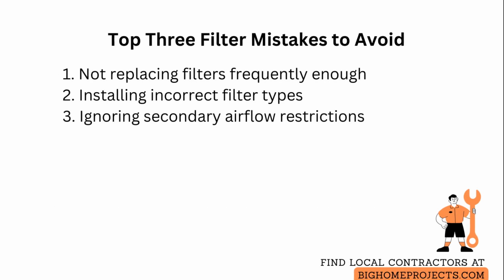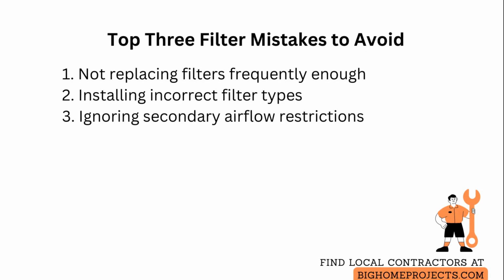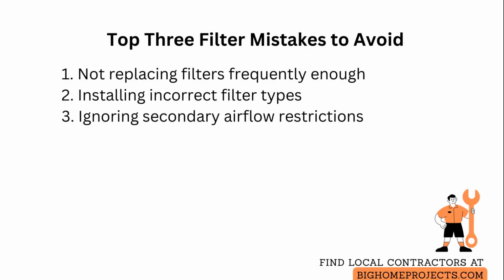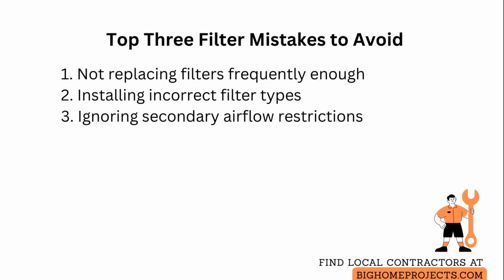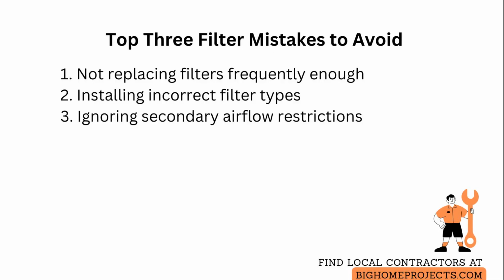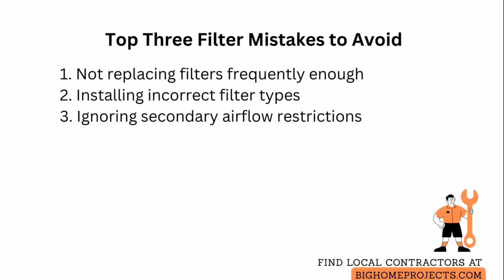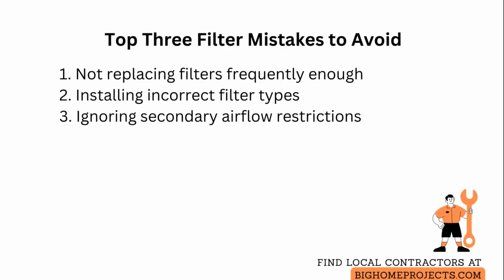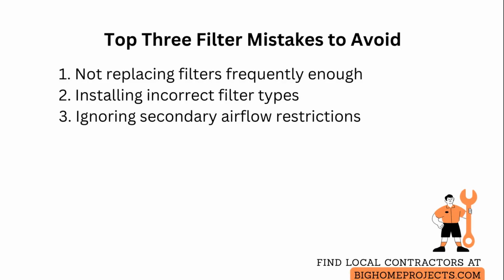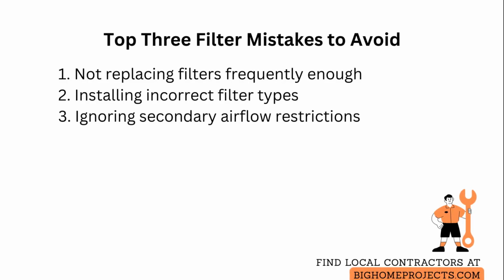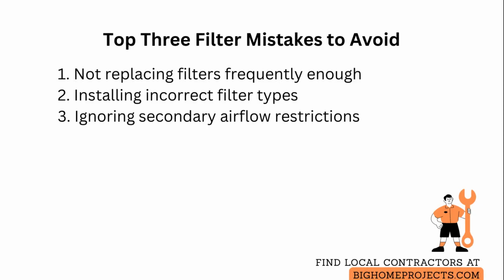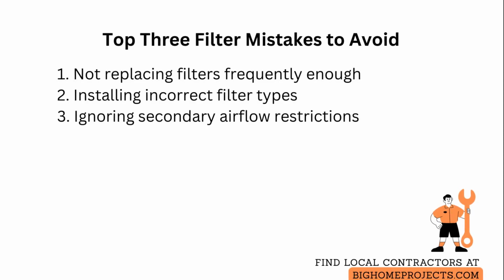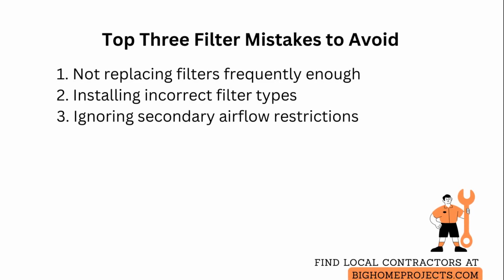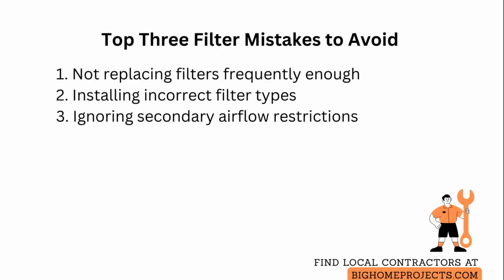The 3 most common issues are failing to replace filters often enough, using the wrong filter type, and ignoring secondary airflow restrictions. When filters are left dirty, the short fix is to replace them immediately, and then set a stricter replacement schedule based on observed loading. If the wrong filter is installed, switch to the size and minimum efficiency indicated by the equipment manufacturer, or use a staged filtration method to preserve airflow.